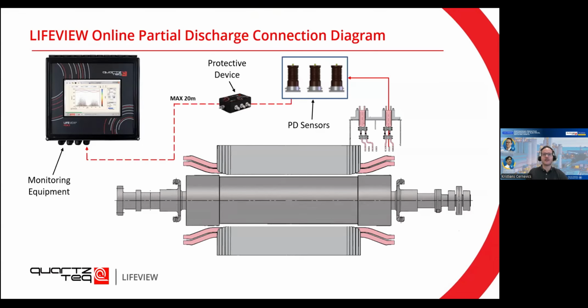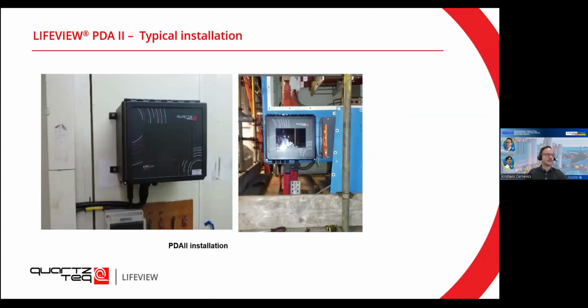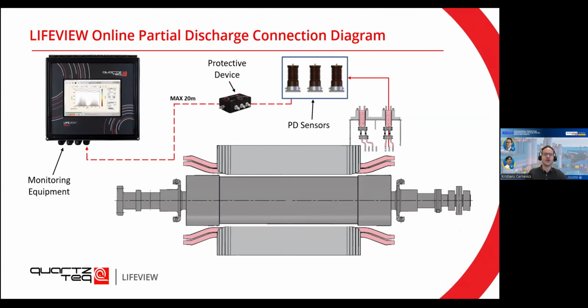So this would be a typical installation of a PDA2, so the monitoring equipment, or you can use a mobile equipment. You have your rotating machine. Through the terminals, you connect sensors. Through the protective device, the signal then goes through, and then it goes to the monitoring equipment. On site, it looks something like this. So you can install it somewhere next to the machine, maybe on the wall. The only limitation here is that you should try to keep it as close as possible to the sensors in order to ensure that the good quality signal goes to the monitoring equipment.